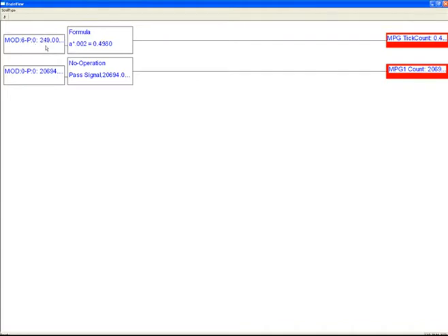This is the timer tick variable coming back from a Mod IO. The Mod IO is kind enough to send a message saying how long each message is taking. And it tends to be in 2 millisecond increments. So I've set a formula which says input A multiplied by 0.002. The answer is shown now when you're viewing a brain.